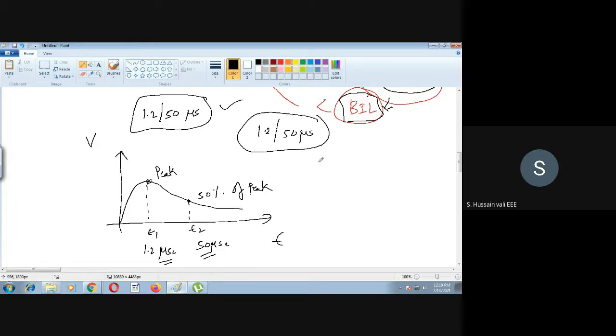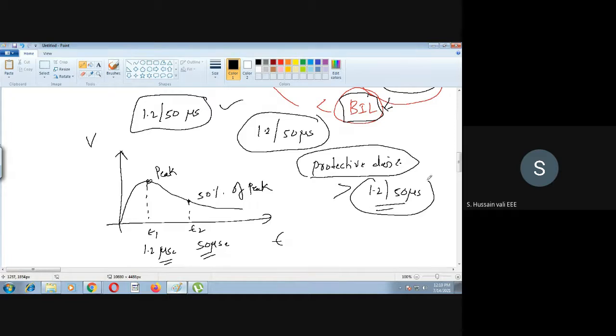Then the protective device which you select should have greater than 1.2 by 50 microsecond, so its insulation level should be greater than this value. What is this value? This is the BIL of the particular system. Now, how do you understand this 1.2 by 50 microsecond? This can be understood from this voltage time graph: this is the time T1, this is the time T2. T1 is the time for the peak, whereas T2 is the time for 50% of the peak. This way you can get the meaning of BIL.